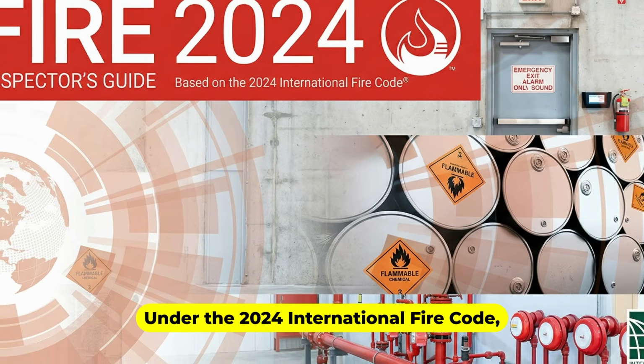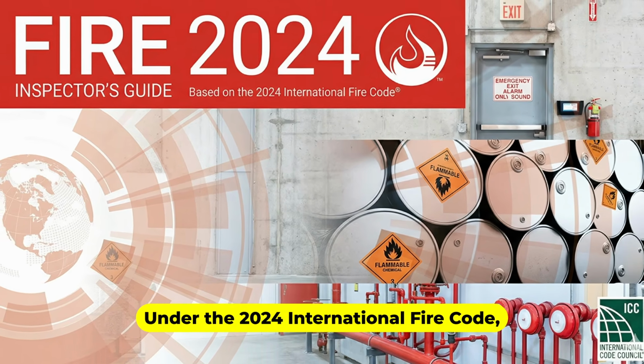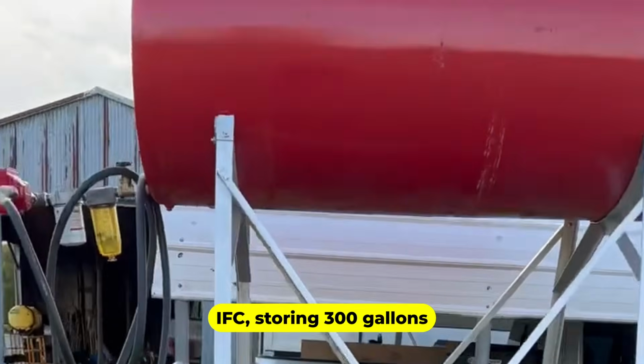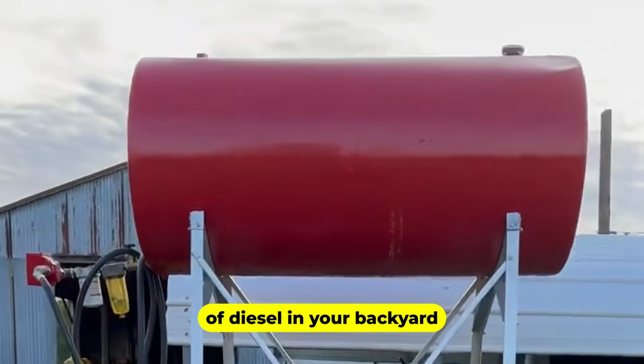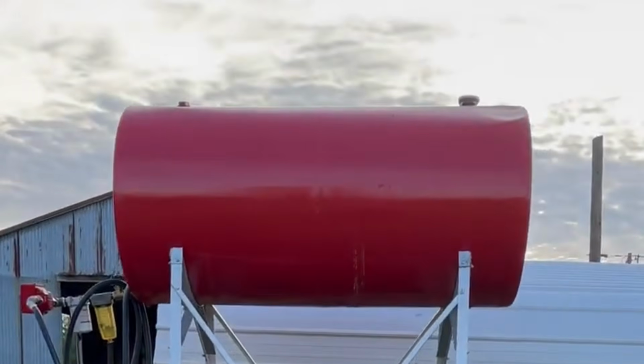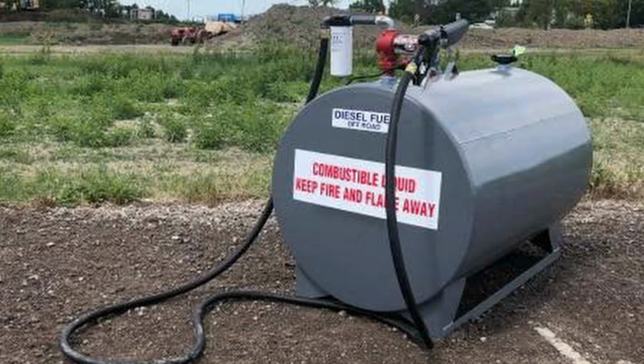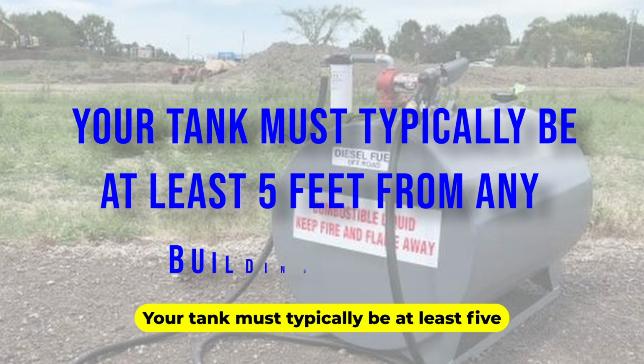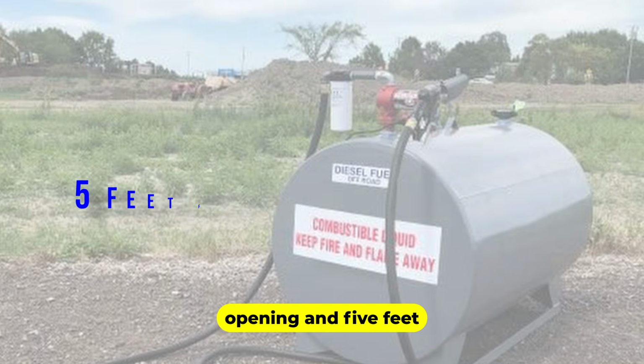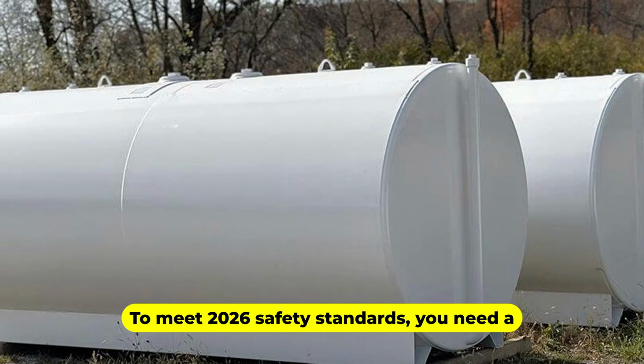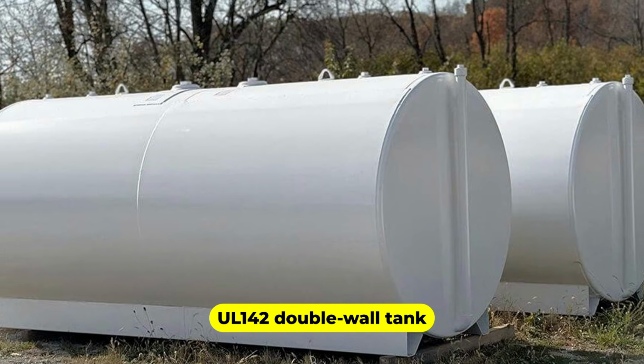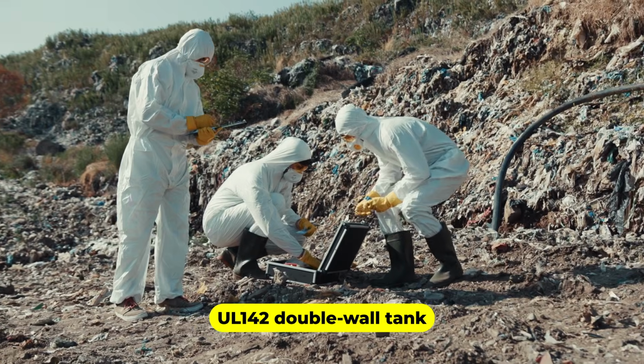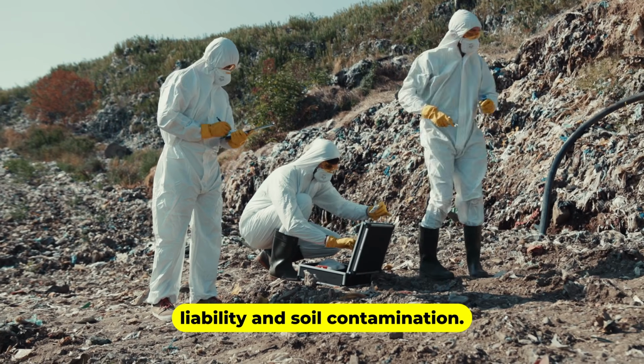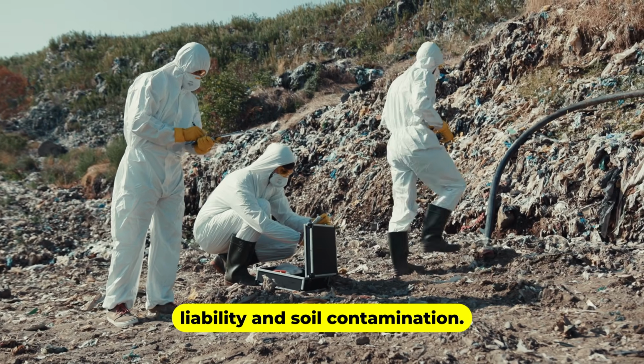Under the 2024 International Fire Code, IFC, storing 300 gallons of diesel in your backyard is a high-stakes legal matter. You are regulated on setbacks. Your tank must typically be at least 5 feet from any building opening and 5 feet from property lines. To meet 2026 safety standards, you need a UL 142 double wall tank to prevent environmental liability and soil contamination.